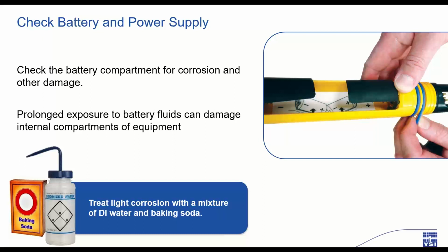But if you catch this problem early, you can clean out the battery compartment using a mixture of DI water and baking soda to neutralize any acid, and so long as the spring is shiny and intact, the sonde should still function. However, if the spring is a greenish or blackish color, then it will likely fail eventually, if it even works at all. In order to prevent this from happening in the first place, just remove those batteries when the sonde is not in use.